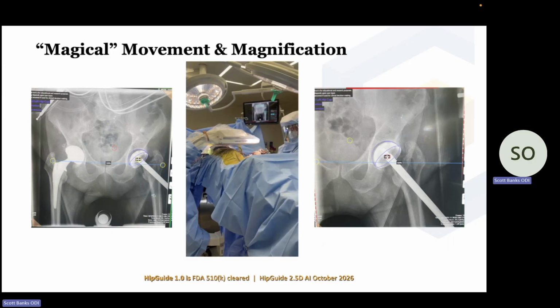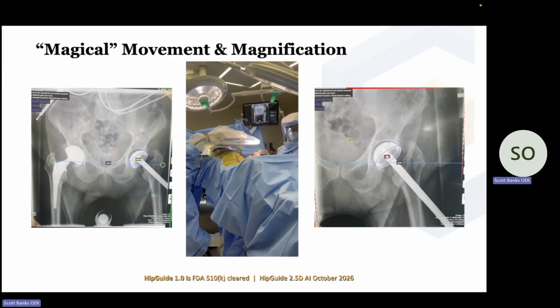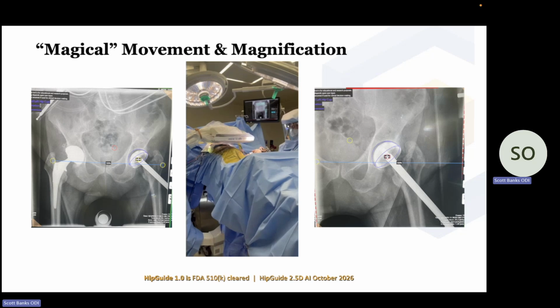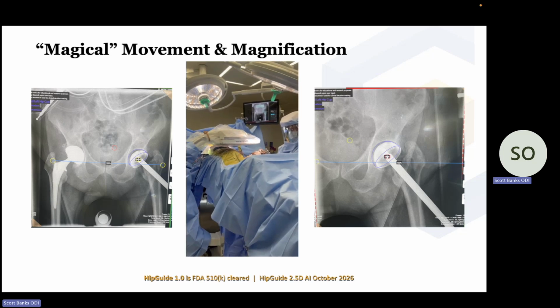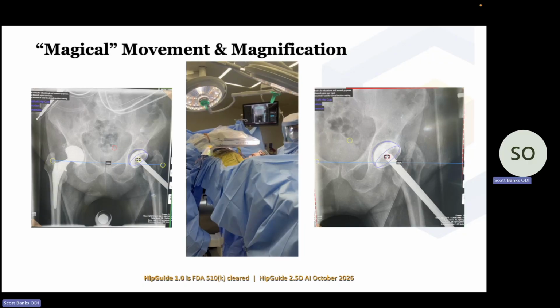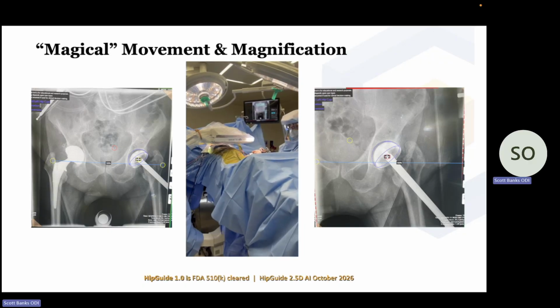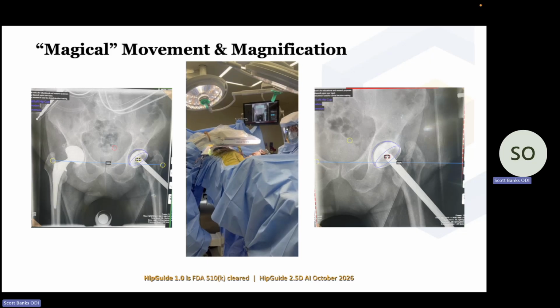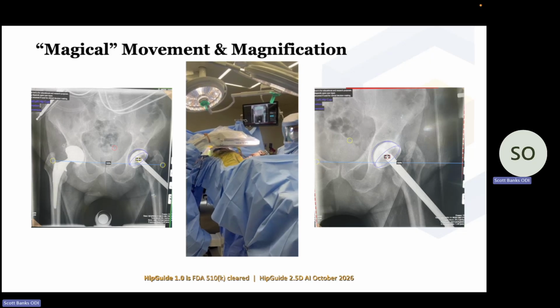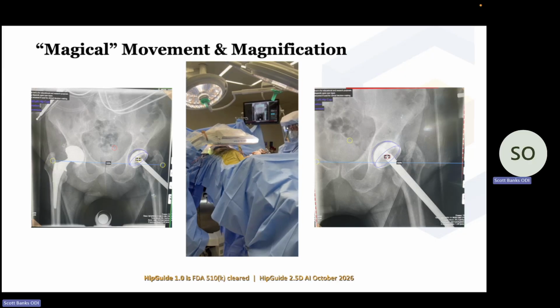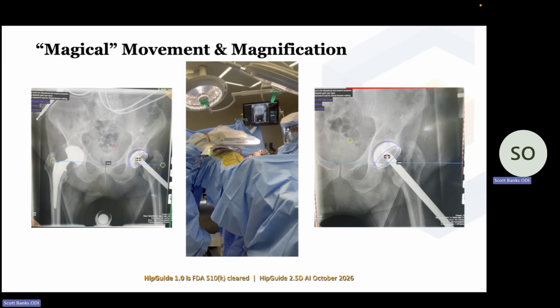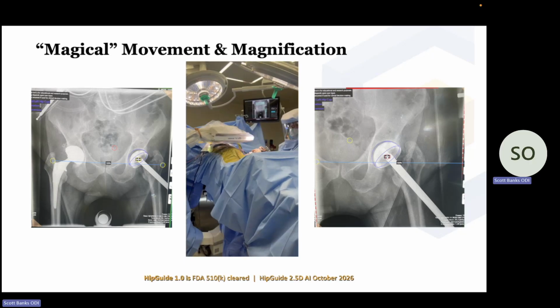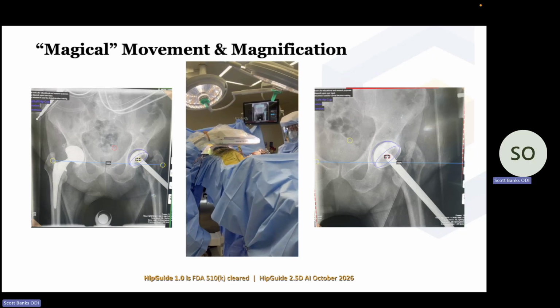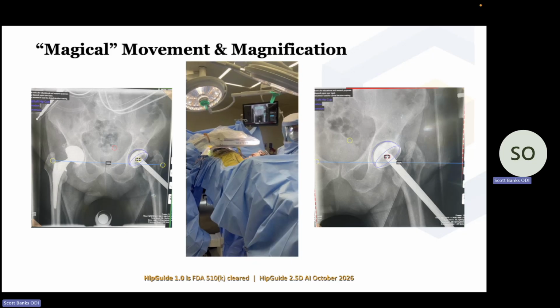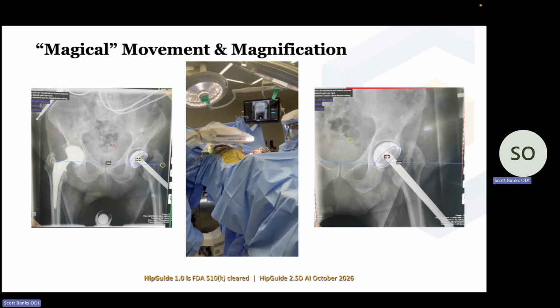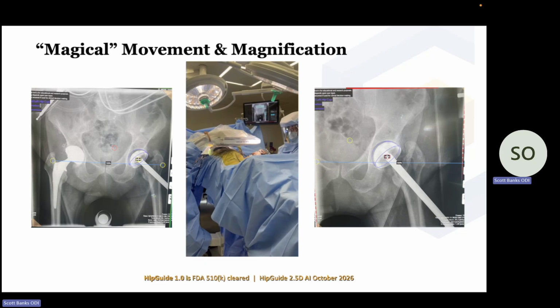One of the key things that surgeons are always asking us is, what about the parallax effect? And what this refers to is that the appearance of an object, such as an acetabular cup, will change as its relationship to the center of the beam moves. And so what is commonly a concern is if the cup, for example, is not at the center of the beam projection, then you can't get an accurate angular measurement for inclination or version. We've taken care of that.